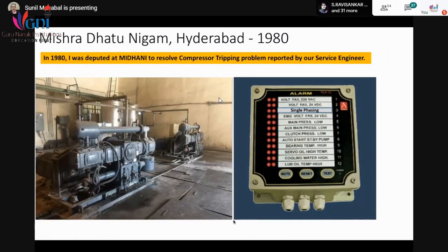So there was an annunciator on that compressor. So I asked them, what is the problem with the compressor trips? What exactly happens? They were not able to tell when it stops. They said it stops at any time while running. So we don't know why it happens. And we also don't get any fault, because it restarts when we reset it and start it.